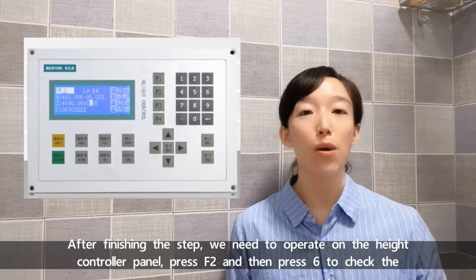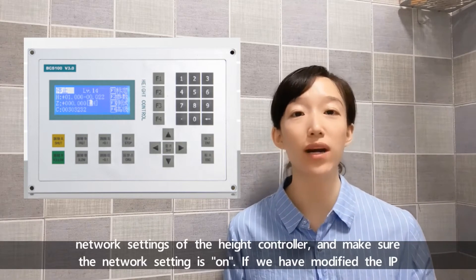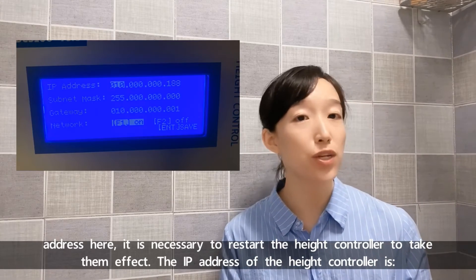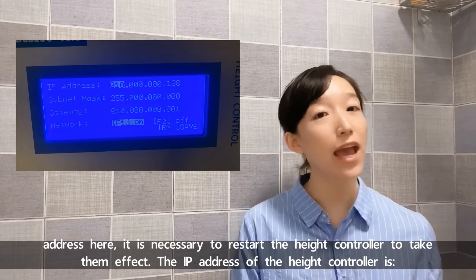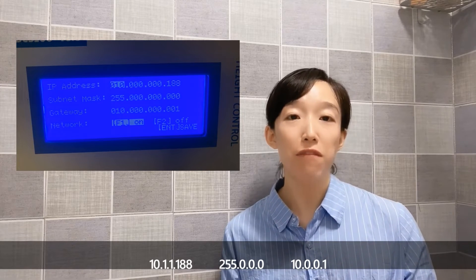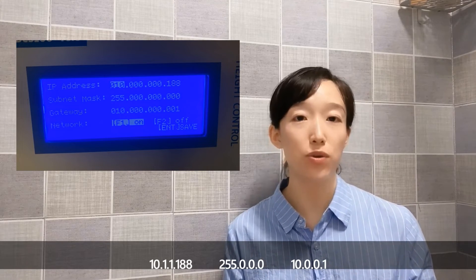Press F2 and then press 6 to check the network settings of the height controller, and make sure the network setting is on. If we have modified the IP addresses here, it's necessary to restart the height controller for them to take effect. The IP address of the height controller should be: 10.1.1.188, 255.0.0.0, 10.0.0.1.